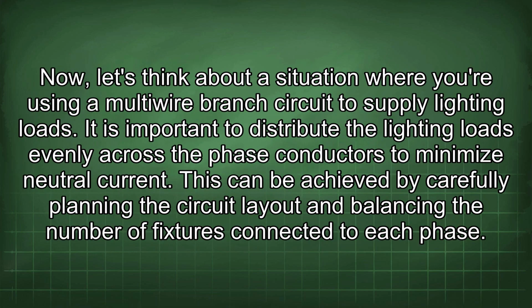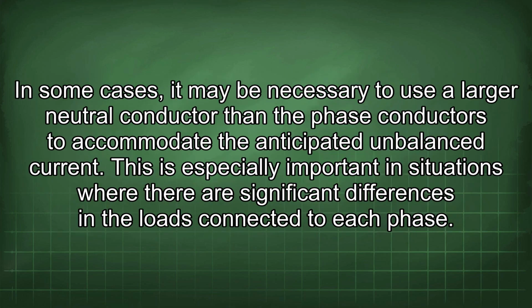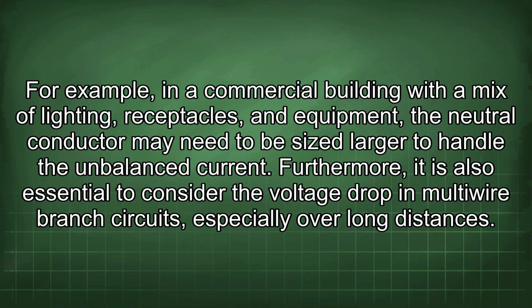Now let's think about a situation where we're using a multi-wire branch circuit to supply lighting loads. It is important to distribute the lighting loads evenly across the phase conductors to minimize neutral current. This can be achieved by carefully planning the circuit layout and balancing the number of fixtures connected to each phase. In some cases, it may be necessary to use a larger neutral conductor than the phase conductors to accommodate the anticipated unbalanced current. This is especially important in situations where there are significant differences in the loads connected to each phase. For example, in a commercial building with a mix of lighting, receptacles, and equipment, the neutral conductor may need to be sized larger to handle the unbalanced current.